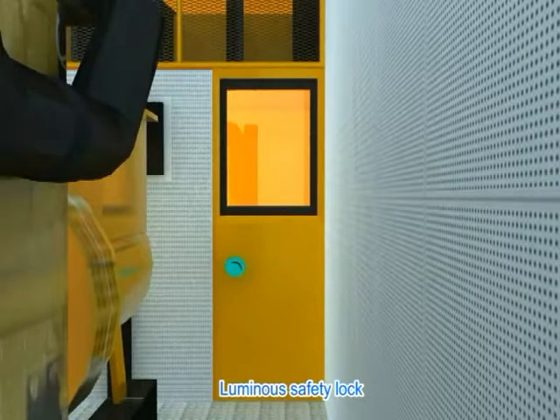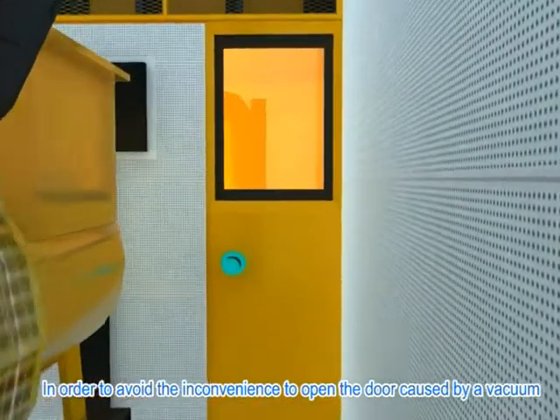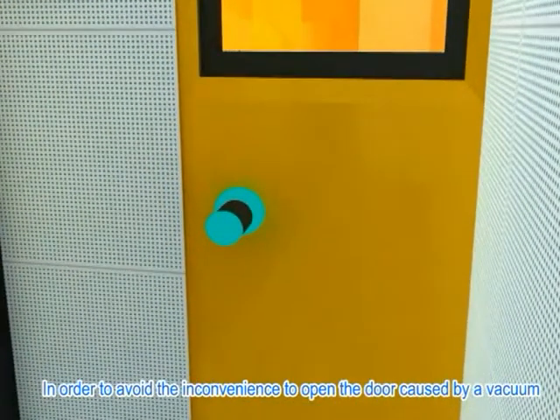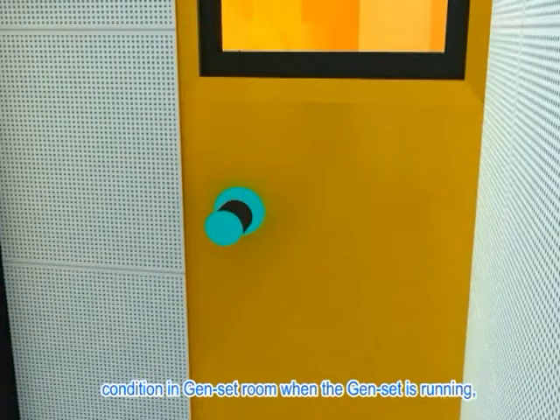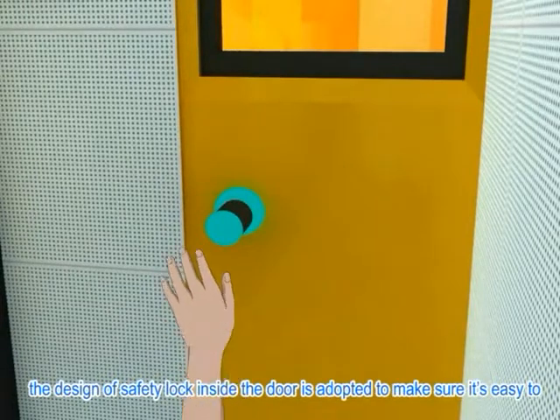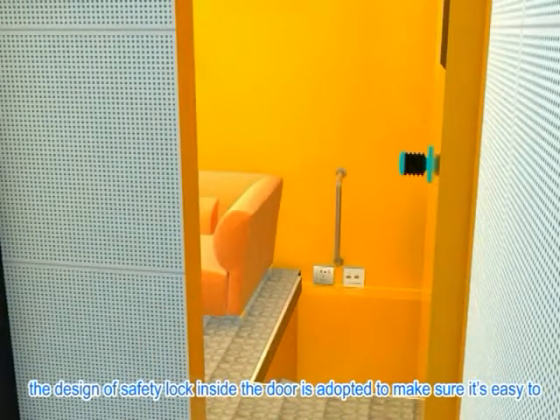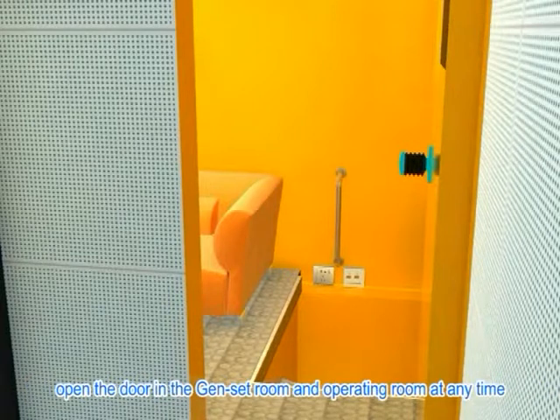Luminous safety lock. In order to avoid the inconvenience of opening the door caused by a vacuum condition in the genset's room when the genset is running, a safety lock inside the door is adopted to make sure it is easy to open the door of the genset's room and operating room at any time.